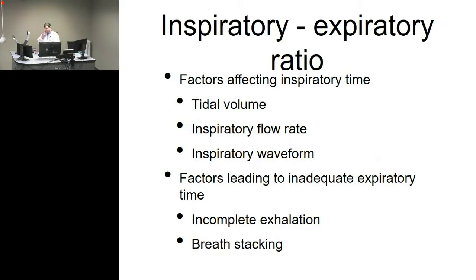And so just for sake of hopefully easy math, again, mental math is not my strong suit, let's talk a little bit about flow and how this works. So we have a flow of 60 liters per minute. Okay? Well, what does that mean? It means we're delivering 60 liters over a minute. Our tidal volume is set at 500 mils. So that means we have half a liter tidal volume.